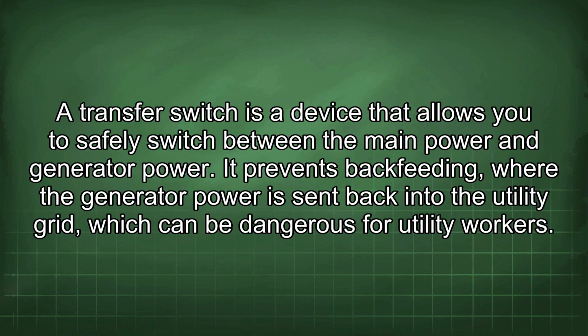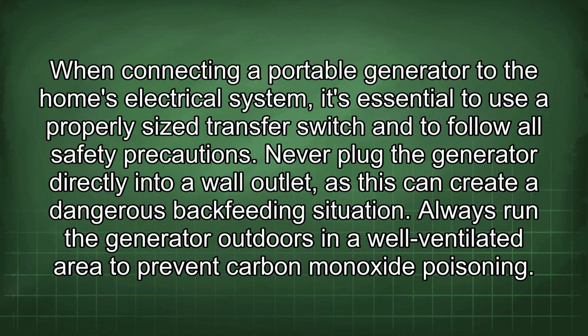A transfer switch is a device that allows you to safely switch between the main power and generator power. It prevents backfeeding, where the generator power is sent back into the utility grid, which can be dangerous for utility workers. When connecting a portable generator to the home's electrical system, it's essential to use a properly sized transfer switch and to follow all safety precautions. Never plug the generator directly into a wall outlet, as this can create a dangerous backfeeding situation.